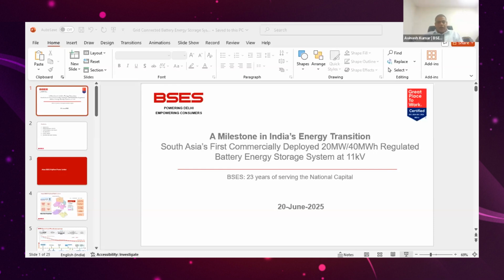Now we are talking about why the battery energy storage system, which we have installed and commissioned, and going forward we are again enhancing our capacity. Why is it required? There is more than 1200 megawatt variation in winter months, which indicates that some equipment is required which can fill the valley as well as shave the peak. The battery energy storage system is best suited for that, and we are enhancing the capacity of BESS.